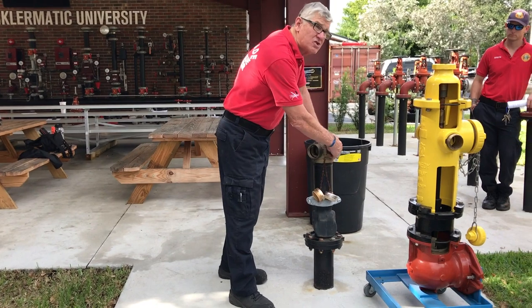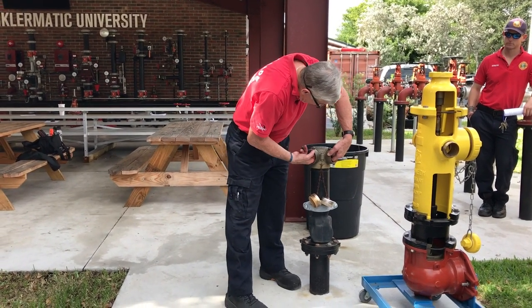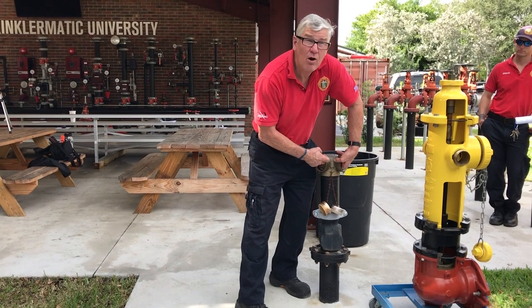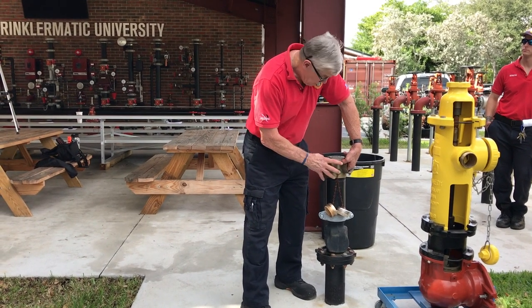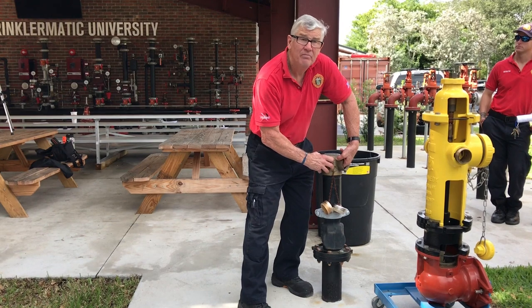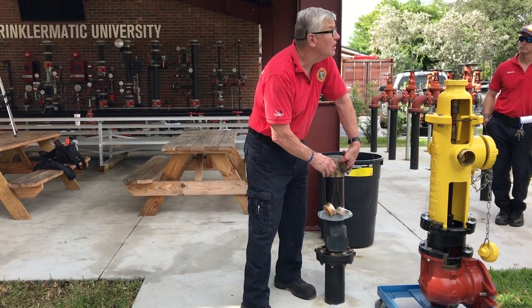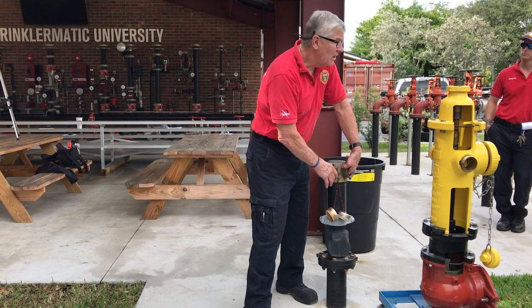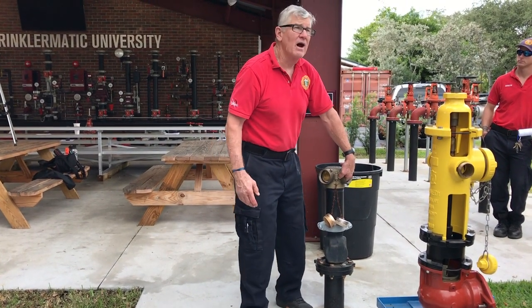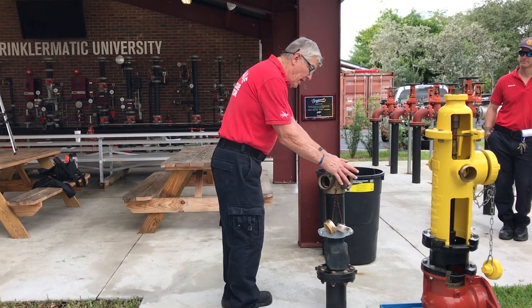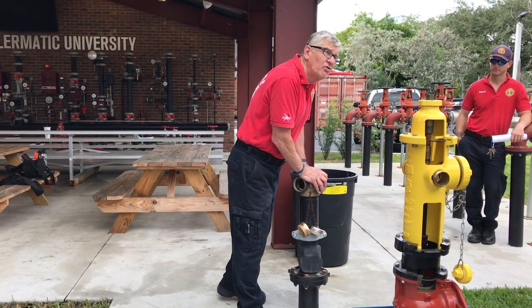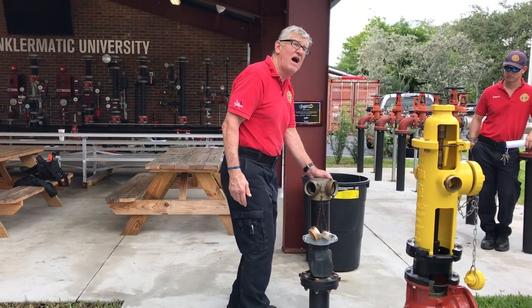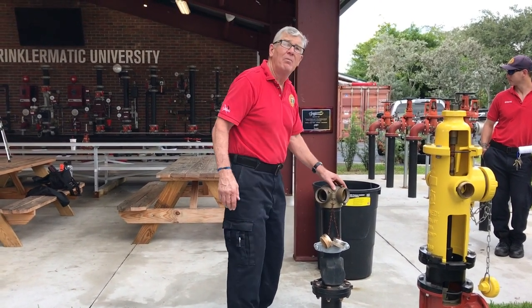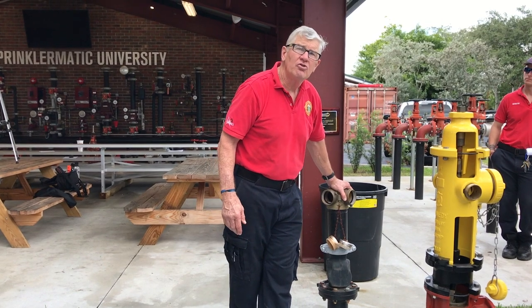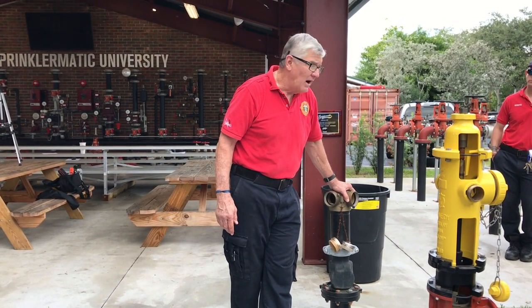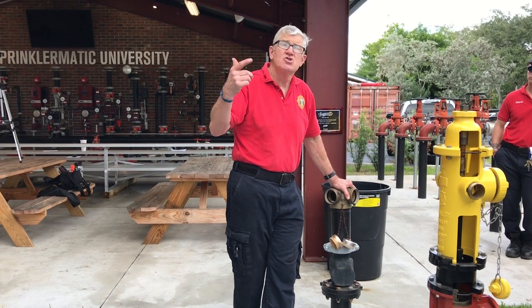If you pressurize one side and this clapper fails to seal off the outlet or the inlet, pressure will build on the male cap, and if you do manage to get it off, it will become a missile and hit you in a sensitive part of your body. Let's leave it at that. So, if we can exceed the pressure on the system, we will open this check valve, and when we walk over to the fire pump later, we will close the check valve for the fire pump on the discharge side.